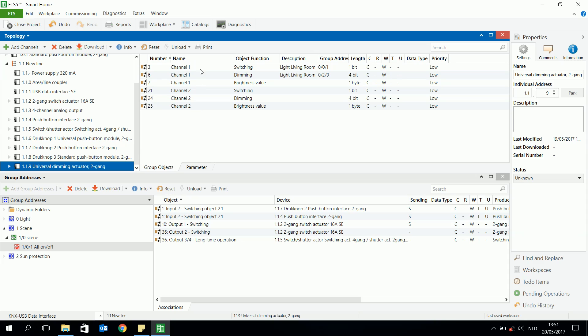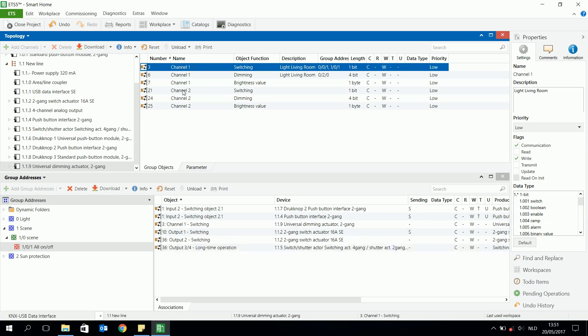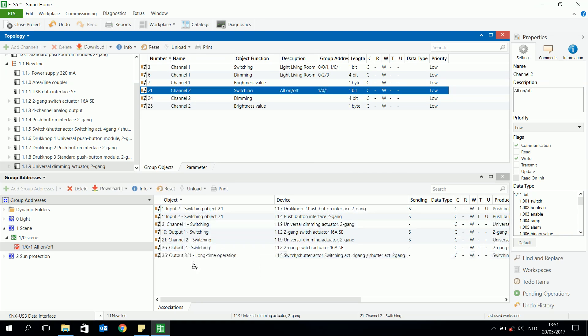I can also use the universal dim actuator to listen to an off or on signal — for example channel 1 or channel 2, the switching object, because it's a one-bit object. The switching object of the universal dimming actuator has already been used and is sending in another group address, so it's no sending anymore here — but that's no problem, because this one has to listen to input 2 of devices 1.4 and 1.7.